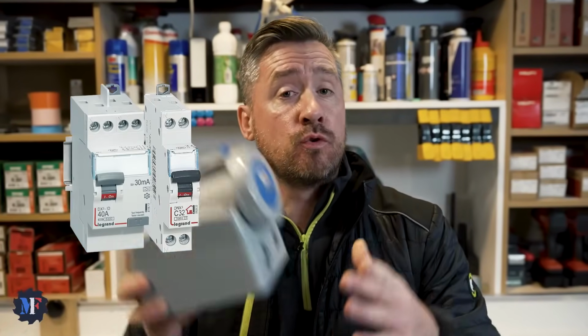You'll need to add a circuit breaker, which costs about 15 euros, and a Type A differential circuit breaker, 40 amps, 30 milliamps, costs around 50 euros. And of course you'll need cable, so go straight for 10 mm2. Even if you only have 3 meters, you might think 6 mm2 would be enough, but honestly, given the power it's going to require, and considering the price difference between 6 mm2 and 10 mm2, just get the 10 mm2.